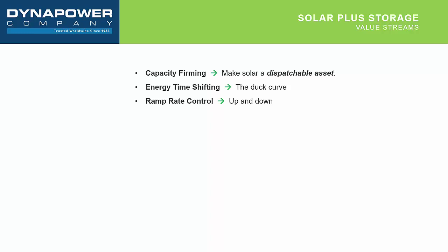This is going to become more and more important as we need to address the duck curve situation in California and emerging in other states as well. And then there's ramp rate control. And this is valuable in areas, Hawaii is probably the best example, where you have a smaller grid where the ramp up and ramp down of your solar array has to be controlled.